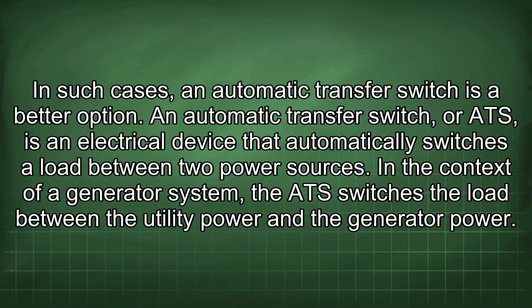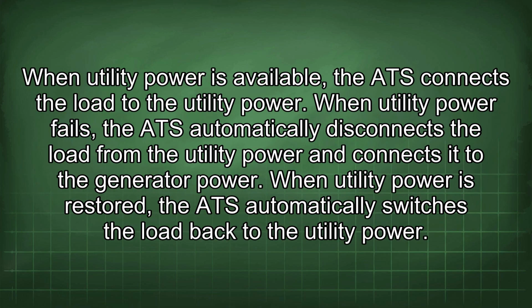An automatic transfer switch, or ATS, is an electrical device that automatically switches a load between two power sources. In the context of a generator system, the ATS switches the load between the utility power and the generator power. When utility power is available, the ATS connects the load to the utility power. When utility power fails, the ATS automatically disconnects the load from the utility power and connects it to the generator power. When utility power is restored, the ATS automatically switches the load back to the utility power.